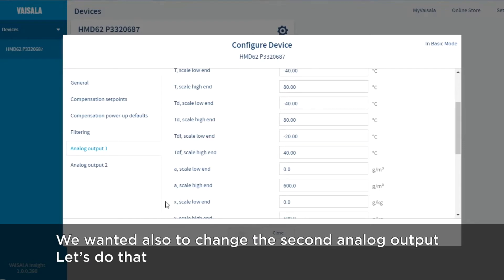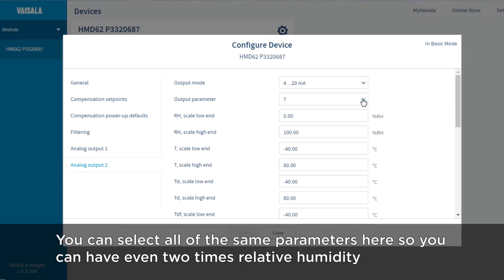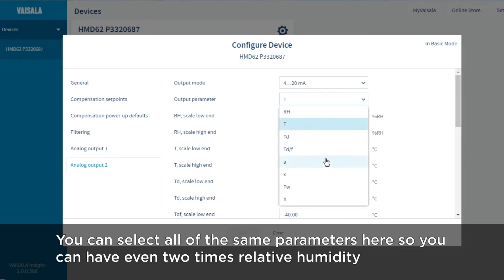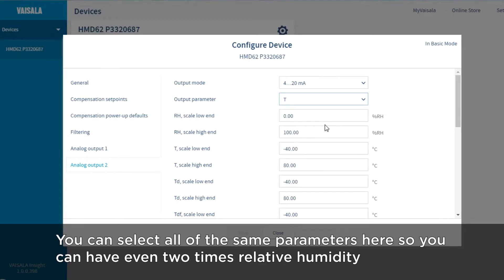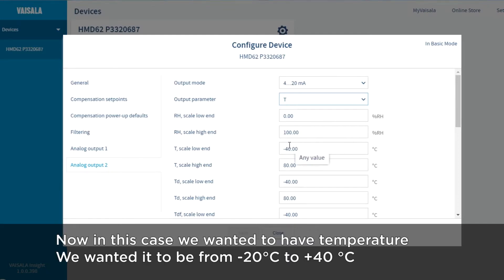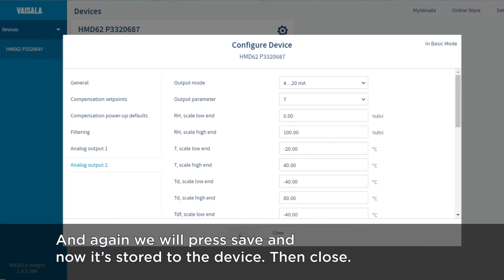We also wanted to change the second analog output. Here again are the default settings for temperature, minus 40 to plus 80 degrees centigrade. Note you can select all of the same parameters here, so you can have even two times relative humidity. But in this case we wanted to have temperature scaled from minus 20 to plus 40 centigrade. We press Save, and now it's stored to the device.